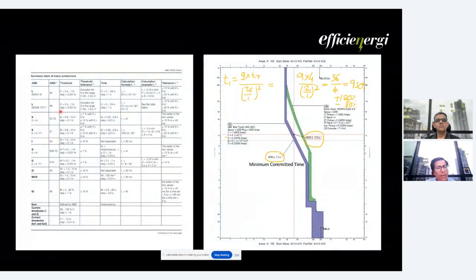So we'll explain how this is to be interpreted. This is particularly the ABB Ekip Touch TCC. This data is taken from the ABB manual. Here you can see for the long time they have given the threshold tolerances, and there are tolerances in the time as well. Here you can see it is starting at 1.05 times. So that care has to be taken, because if 4000 is the limit at which we have to start our operation time, then we cannot set it at 4000 ampere. We have to set it lower than 4000 ampere. Then only the purpose of the protection will be achieved.